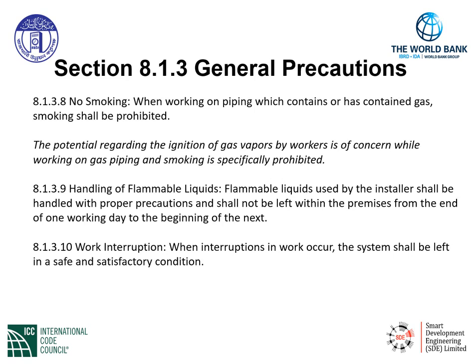Handling of flammable liquids is given to us in section 8.1.3.9. Flammable liquids used by the installer shall be handled with proper precautions and shall not be left within the premises from the end of one working day to the beginning of the next.